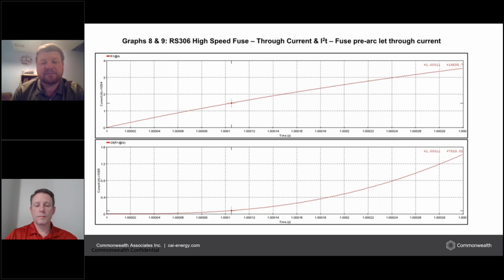That's that top right value you see there. It's about 14 and change. I know the text is very small. I apologize for that. But that's where we found that our fuse was blowing on this DC curve. So in this particular case, the fuse was much faster than the prospective fault current. But based on our experience, that is not always the case. And sometimes the DC prospective fault current rise is faster than the fuses.